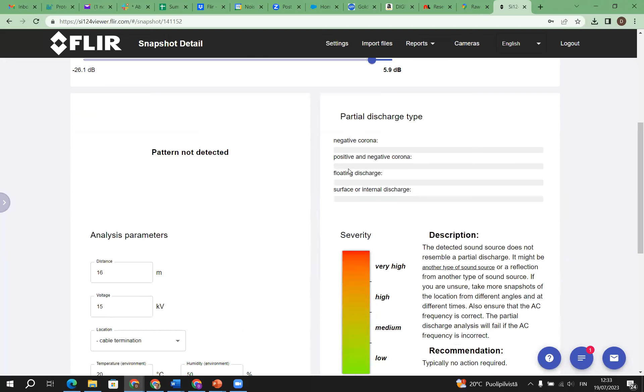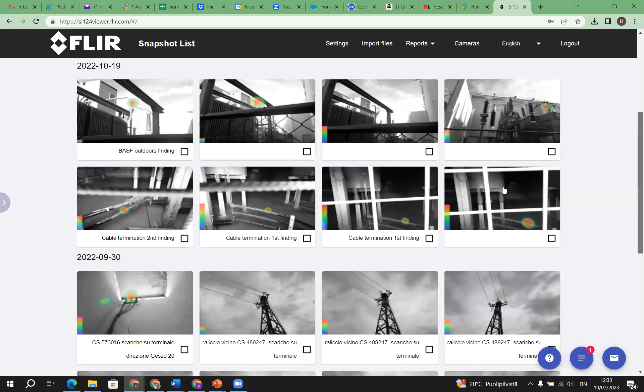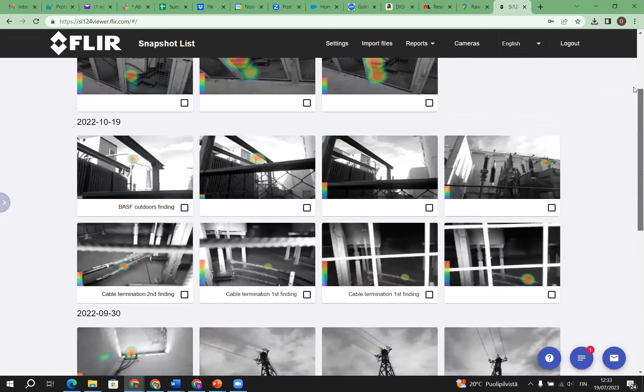So here's an example of a harmless partial discharge. You see, it's not even giving any information, I think because it was so small. So there's a PD, but no severity given here. As you see, the camera can determine and find many partial discharges that are not severe at all, but it can also find partial discharges that represent a real problem to the customer. That's actually a very good selling point.